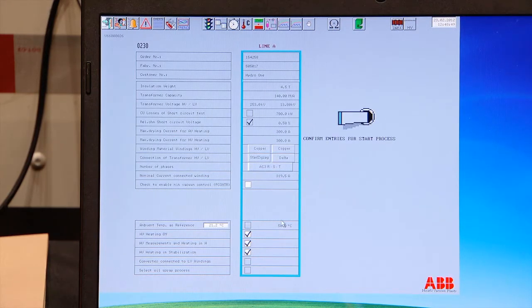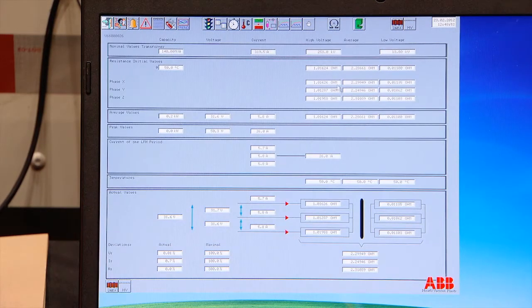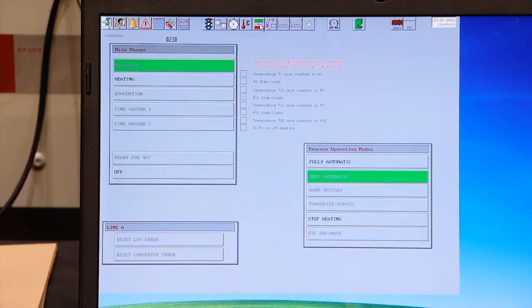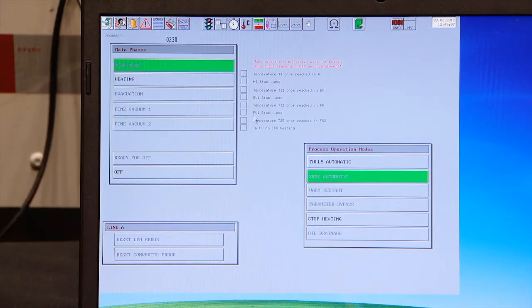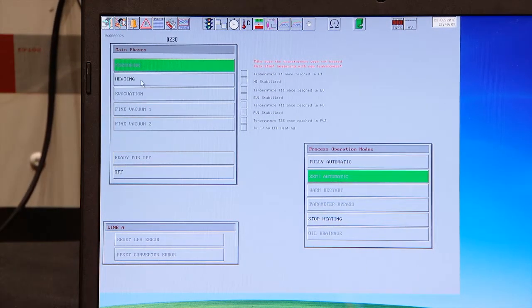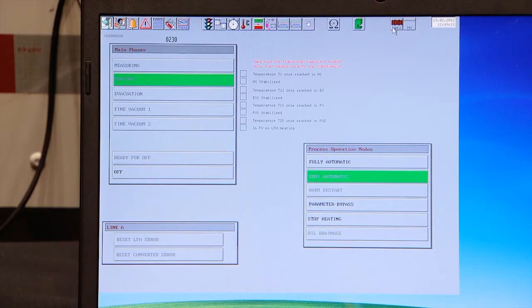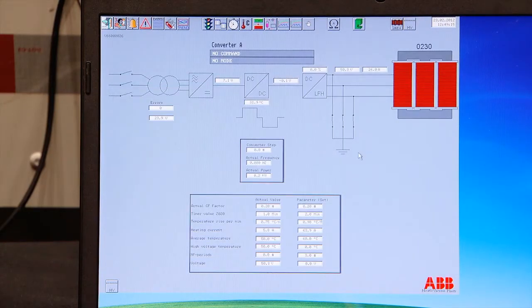Since we are preheating the transformer, the resistance values are higher than before, but they are okay. Low deviation between the phases, and we are ready to go on. So go back to the start and stop page. From the start and stop page, we click the heating button. The converter will wait a little bit, and then he will go on, start heating.